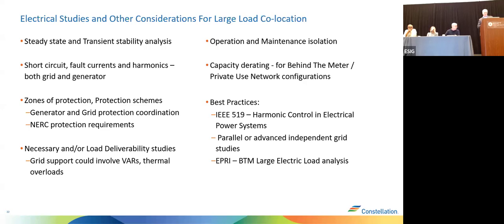I'd also mention on this page, on the right-hand side, capacity derating, and perhaps this is primarily a PJM type of an issue, but if you have a fully isolated load in the PJM market, it's required that you delist capacity for the unit, meaning you don't get a capacity payment from the grid at the same time that you are fully isolated from the grid for that customer.